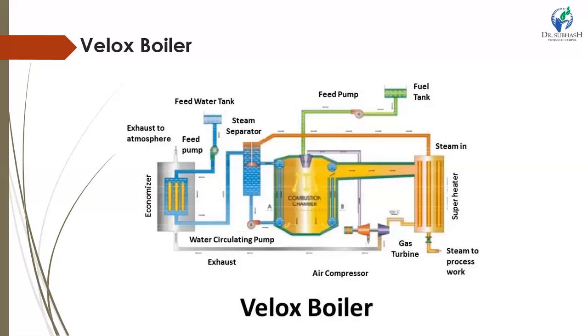The steam water mixture then passes to a separator which is designed in such a way that the mixture enters with a spiral flow. This produces centrifugal force, due to which heavier particles are thrown out on the walls. This separates steam from water. The saturated steam is then superheated and supplied to the steam turbine.